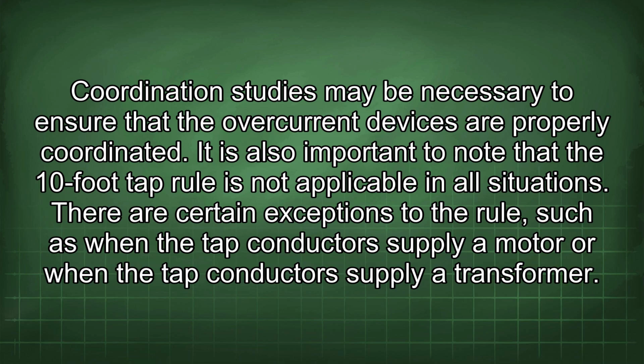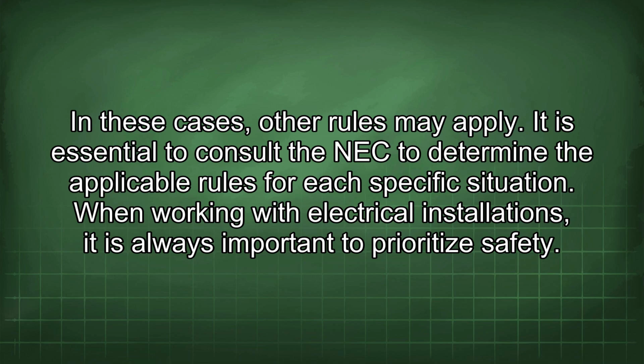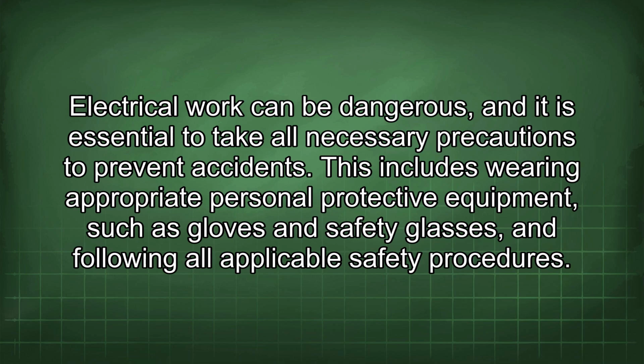It is also important to note that the 10-foot tap rule is not applicable in all situations. There are certain exceptions to the rule, such as when the tap conductors supply a motor or when the tap conductors supply a transformer. In these cases, other rules may apply. It is essential to consult the NEC to determine the applicable rules for each specific situation. When working with electrical installations, it is always important to prioritize safety. Electrical work can be dangerous, and it is essential to take all necessary precautions to prevent accidents. This includes wearing appropriate personal protective equipment, such as gloves and safety glasses, and following all applicable safety procedures.